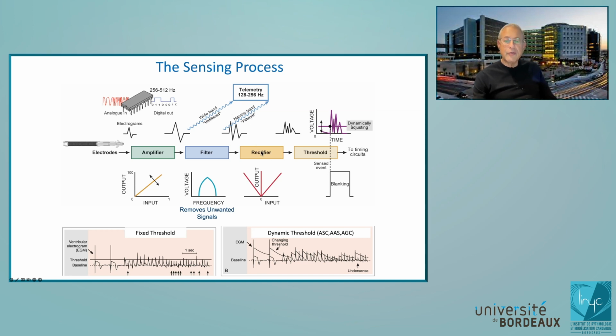And then just so you know the rest, which is not important for your clinical work, the signal is then what we call rectified. That means anything that's negative is turned into a positive signal. The reason for that is simple engineering simplicity: now we only need one threshold. We don't need a positive and a negative threshold to keep track of. A circuit that just takes the absolute value is very simple to throw into your electronics, so we wait until the signal exceeds the value of the sensing threshold, which may be changing with time, but at any one time it's at a certain value, and that's when we get a sense.